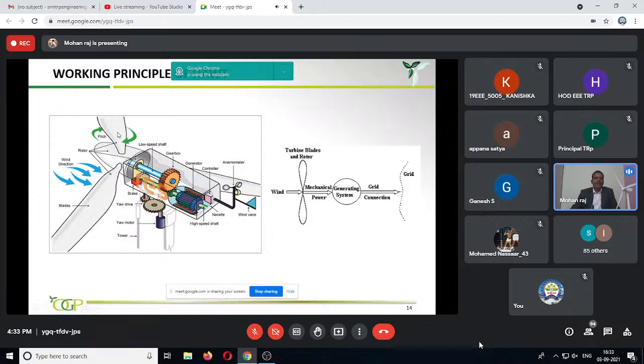And this is the blade, and the blade rotates from 0 to 90 degrees. So when the turbine is at standstill and there is no generation, the blade will be at 80 to 90 degrees. It shifts to 80 to 90 degrees. It will pass on the wind. It will not capture the wind to convert the kinetic energy into mechanical energy.